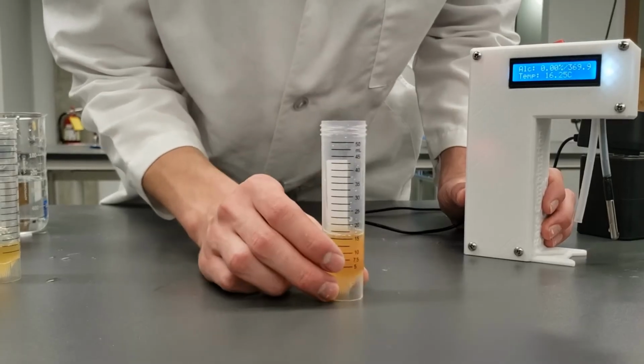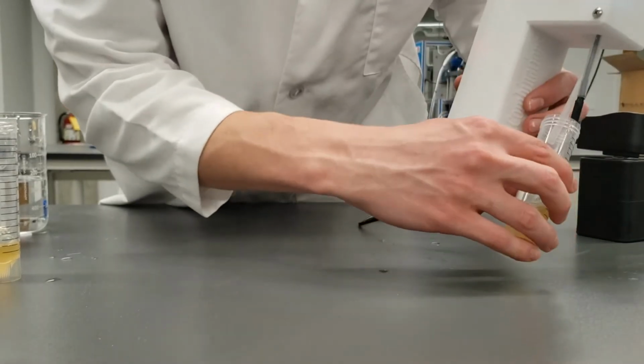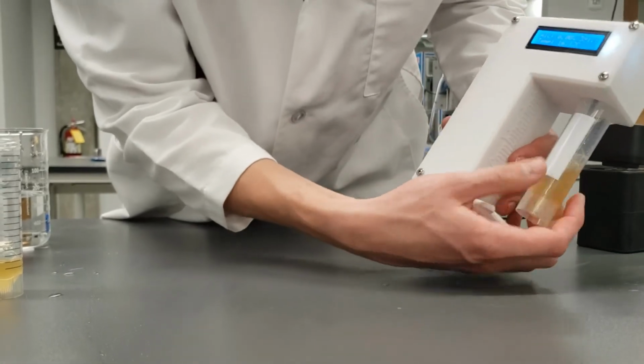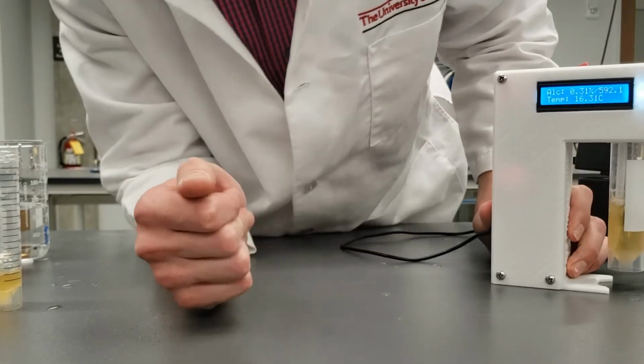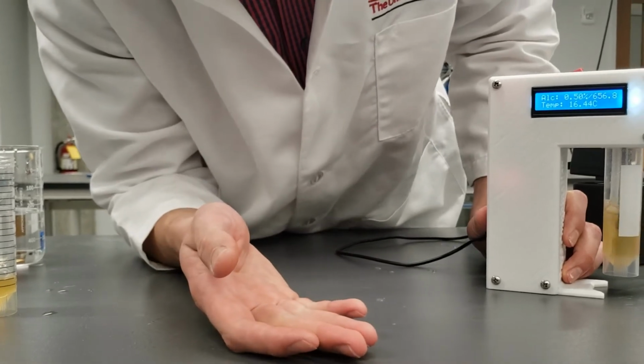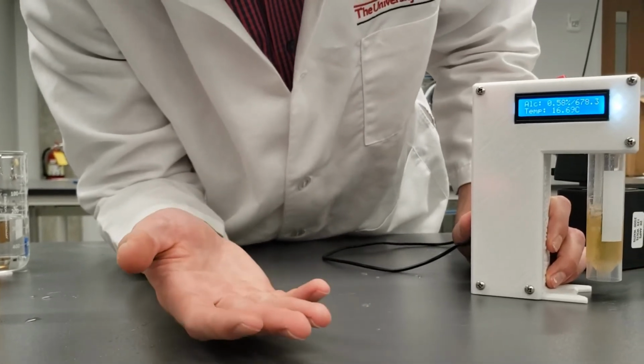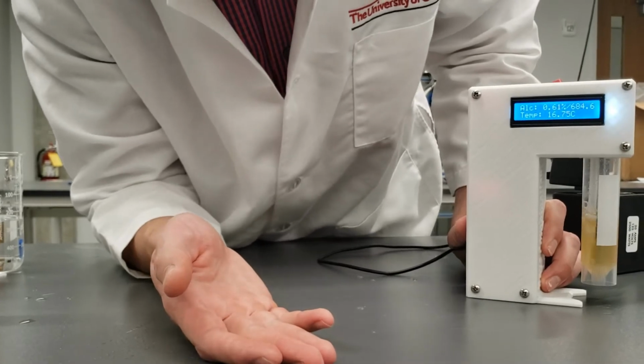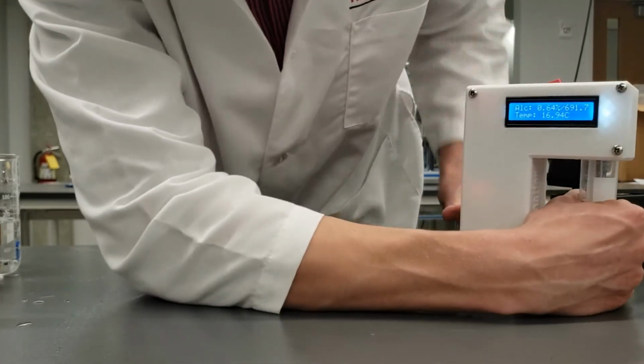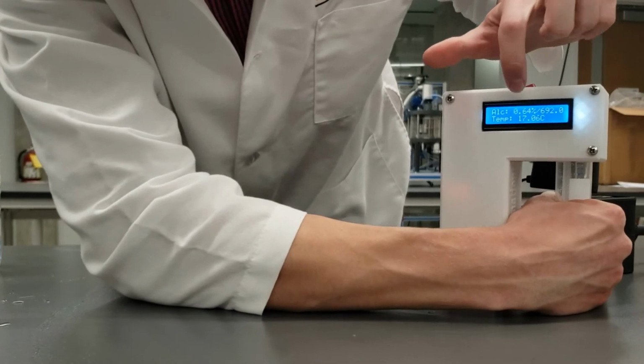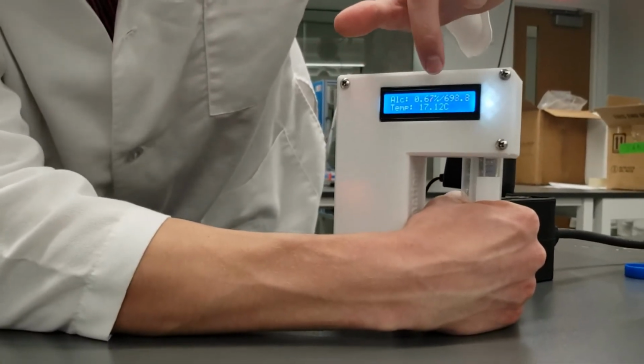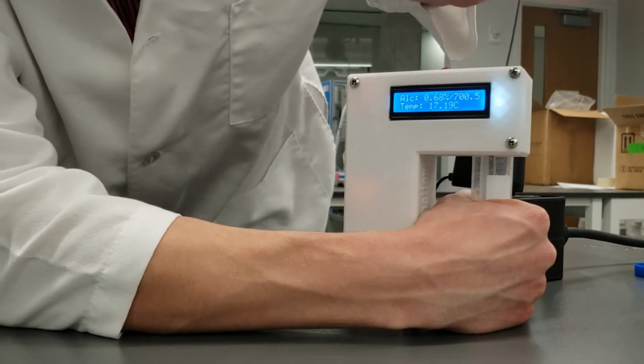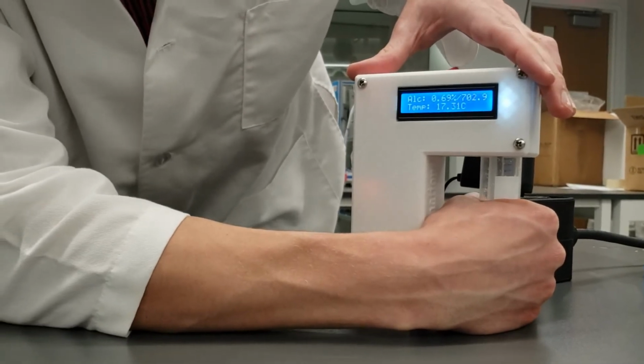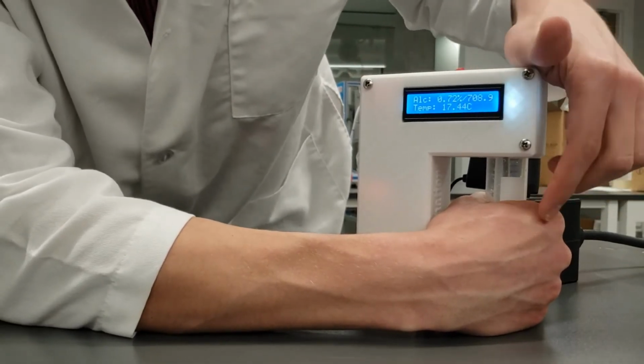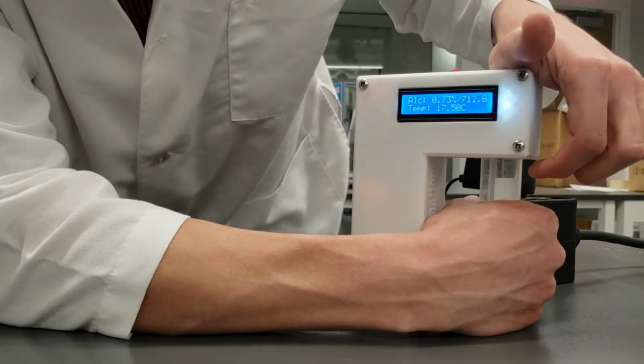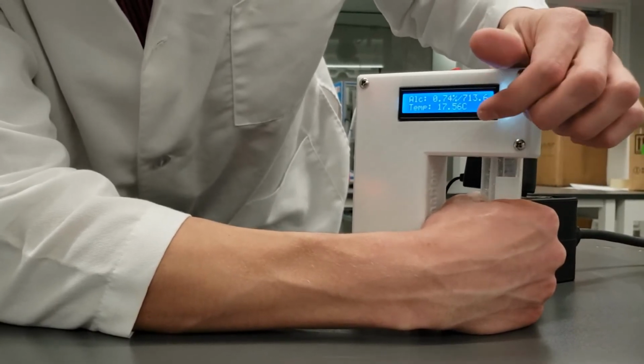Okay, so we're gonna take our sample that we just poured and test it in the detector now. So this is pretty exciting. I actually haven't tested my own kombucha because I don't care too much about what the alcohol content is, just because I'm drinking it for myself, and 1% isn't gonna do any harm for me. So as you can see, the temperature of our sample is 17 degrees C, which is much lower than the calibration temperature that we found, which was 19 degrees C. So you can see me right here just warming up the sample with my hand. Hopefully we can get it up to 19.